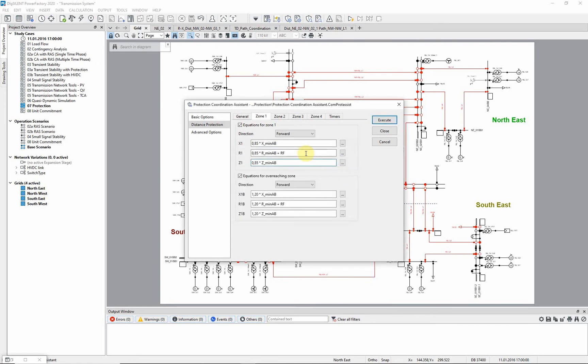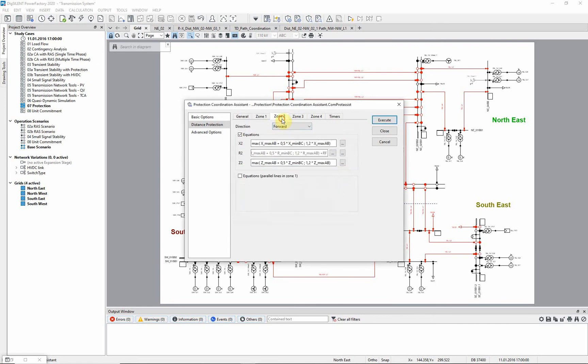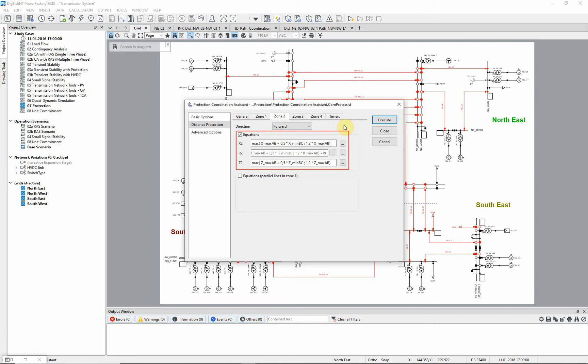As shown in the equations for zone 2, the operator max can be used to enhance the flexibility. In this case, either the longest first line plus 50% of the following shortest line is used, or 120% of the longest first line.